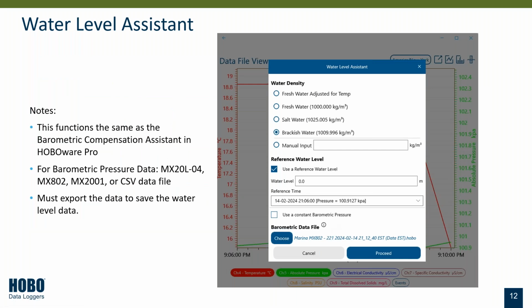So here's a brief look at the water level assistant. It's very similar to the barometric compensation assistant that many of you may have used in HoboWare Pro with our prior U20 series loggers. You enter in a water density, reference water level and time, and then you can link in a barometric data file for barometric pressure. We do recommend that you have a logger deployed nearby in the air, at least within 10 miles is good enough. So you can use one barometric logger with several water level loggers deployed in the area. That barometric pressure logger makes a difference with the readings. Those barometric pressure changes can make a difference of 6 inches, maybe even up to a foot in your water level readings if you don't compensate for it.